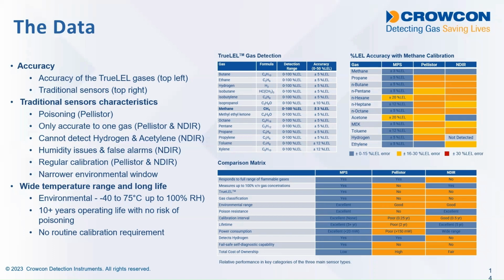However, the MPS sensor is able to work up to 70 degrees Celsius, and the MPS sensor will last more than 10 years. It does not need calibration for at least 5 years. So the MPS sensor does not need calibration. Its calibration is guaranteed for 5 years, which means operationally it's a huge cost saving not having to use test gas to calibrate your sensor. Pellistors require calibration every 6 months at the absolute minimum.